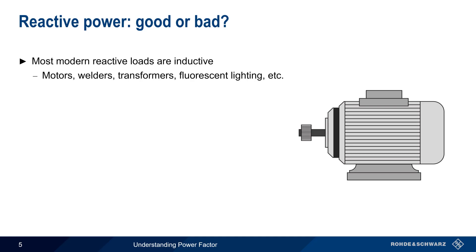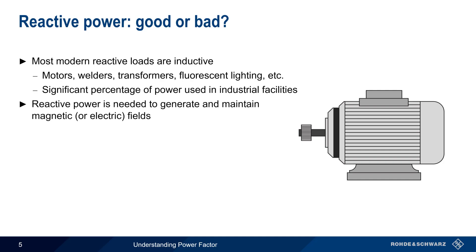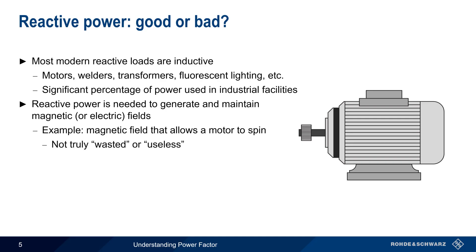Let's talk a little bit more about reactive power. First, most modern reactive loads are inductive, not capacitive. This includes things like motors, welding equipment, transformers, fluorescent lighting, etc. These kinds of inductive loads consume a significant percentage of power delivered to industrial facilities. Reactive power is the power that creates and maintains magnetic or electric fields. Since a motor requires a magnetic field to spin, this reactive power is not truly wasted or useless, even though it's only being temporarily stored and not being consumed by the load.